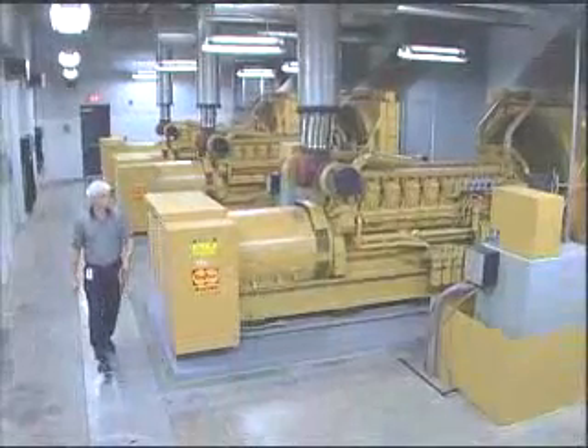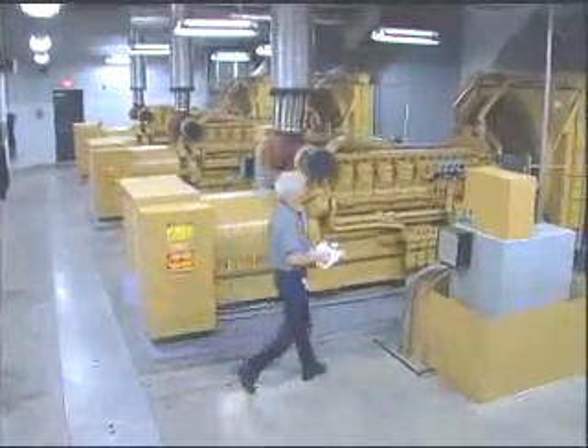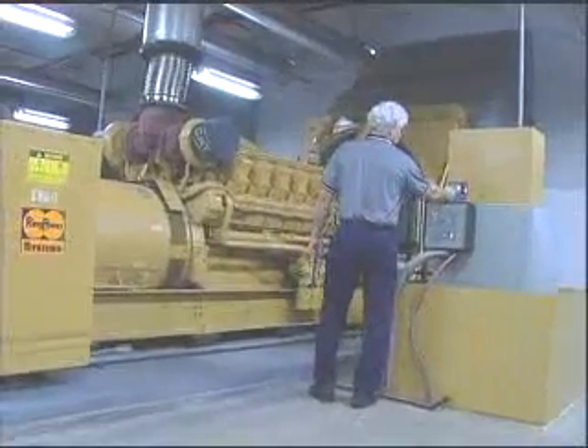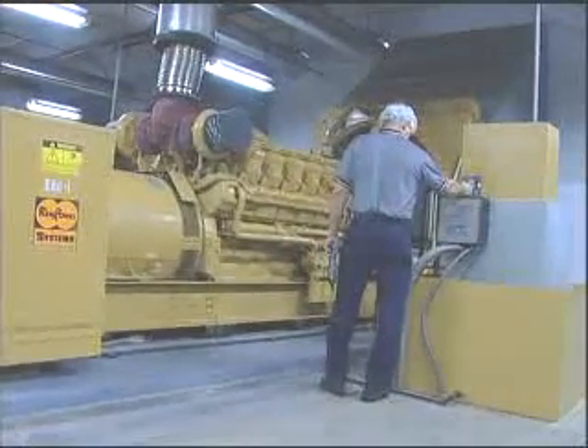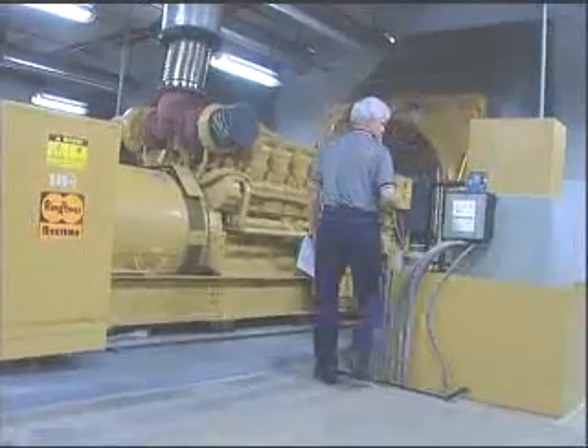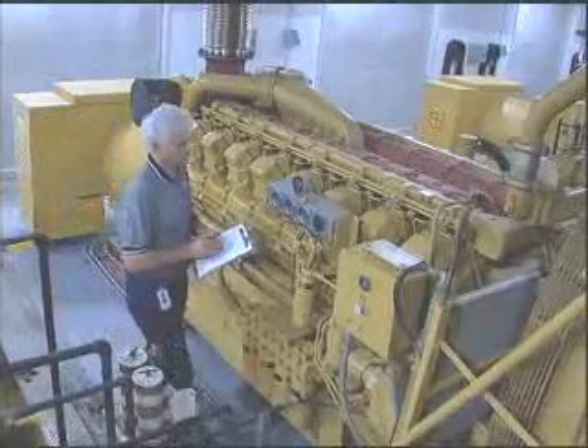Copper and fiber for voice data enter the building at 2 separate locations, and they are reinforced with concrete conduit systems. The AITC has the capability to stand alone for 25 to 30 days. We can do this by the use of our 3 emergency backup generators. Each generator has a respective 10,000-gallon fuel tank. Any one of these generators is capable of supplying the total building load.